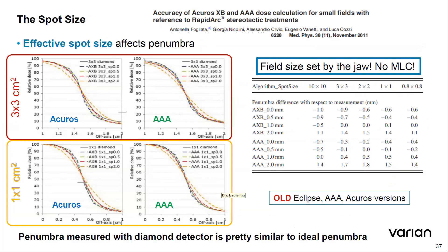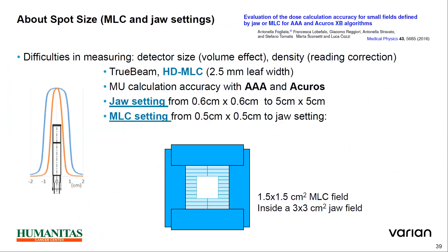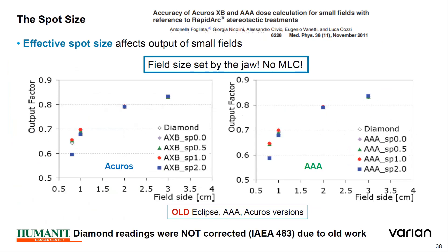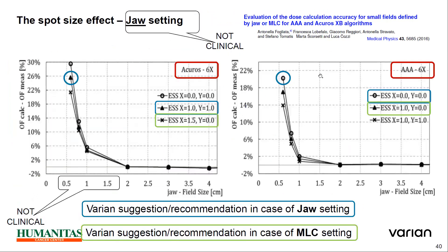These are the results for the MLC settings. Remember, the old version of Eclipse has different values compared to the new version. The MLC design is the same, but the modeled properties of the MLCs differ between old and new versions. Varian recommendations apply in the case of jaw setting and MLC setting.